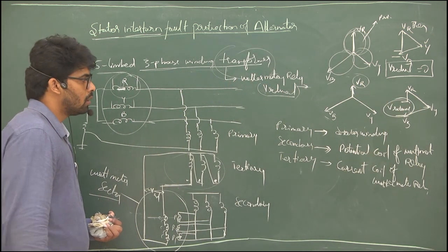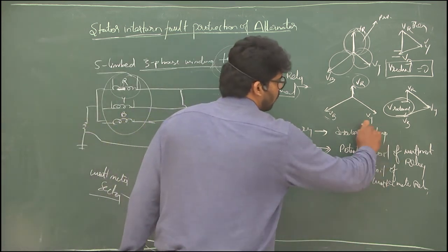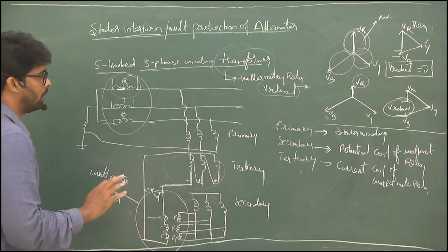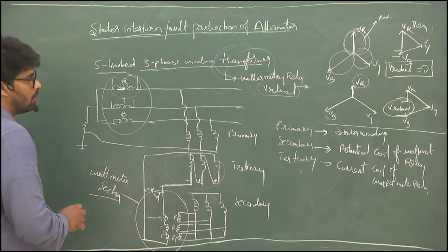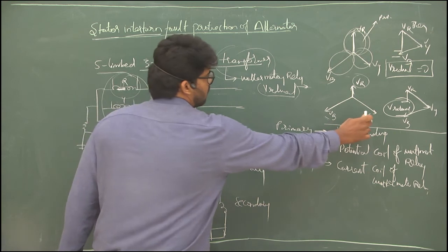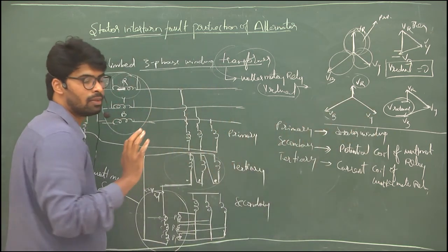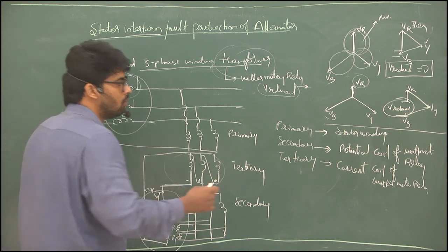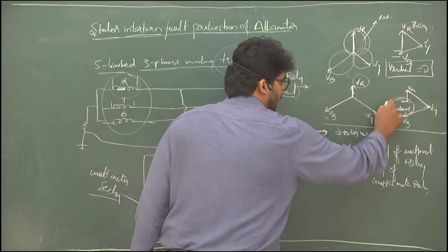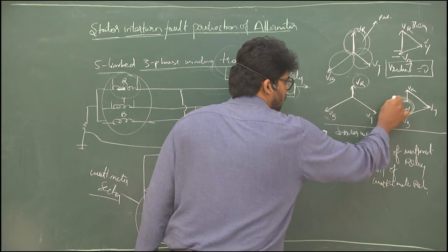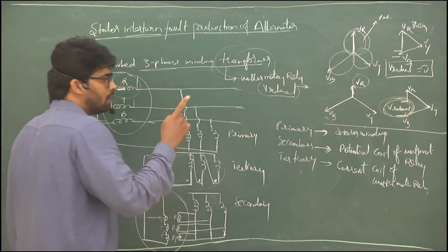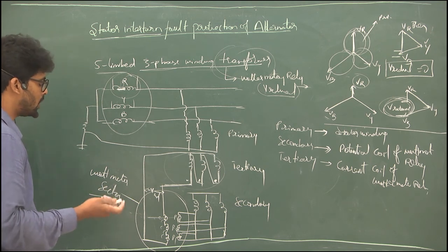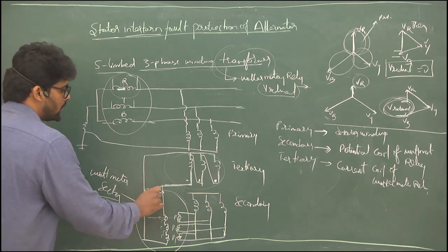The main thing to understand the working of any system is that we depend on phasors. By looking at the phasor diagram, you have to analyze that if there is a gap, the complete delta is not forming, which means there is a production of residual voltage.